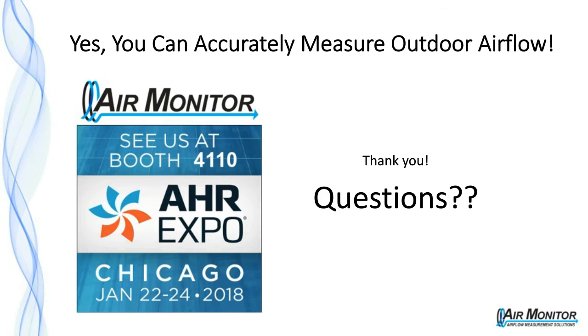So the next question is, when calibrating a louver, what field technique do you recommend? It really depends on the application, what's available. Obviously, there's probably not going to be any ductwork where you can do a standard field traverse. But what we would recommend is a face velocity traverse. Right in front of the louver, we split it into equal areas, take a measurement in the center of each of those equal areas, average it, and figure out what the average velocity is across that louver.